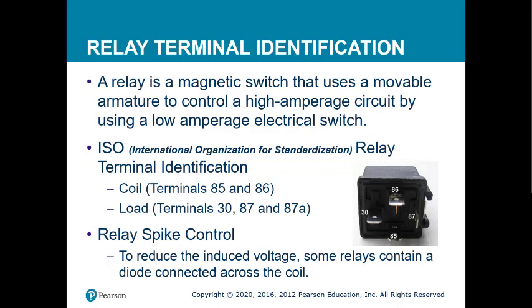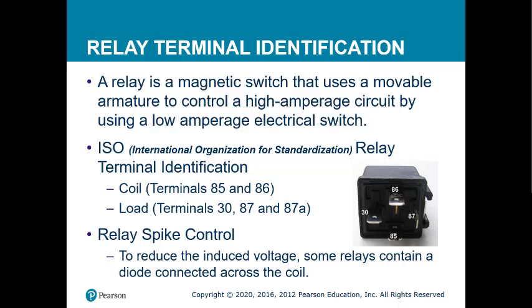It really helps if you understand what these terminals do, so that way you can understand how to test it. So the coil inside that creates the magnetism, those two terminals are 85 and 86. The load side of the relay, which is the switch side of the relay, are terminals 30 and 87. 30 would be the input, 87 would be the output to the load.